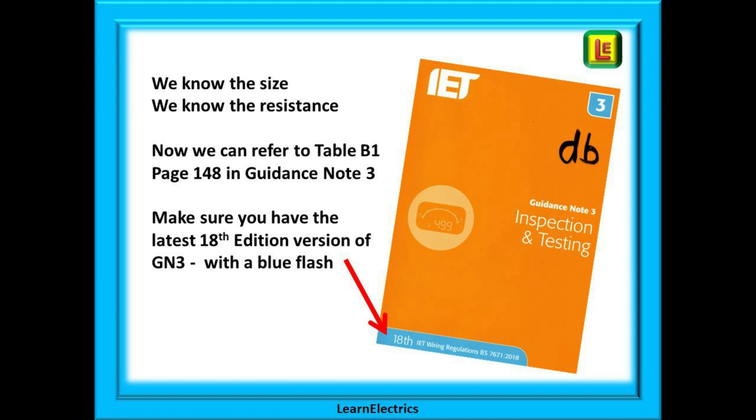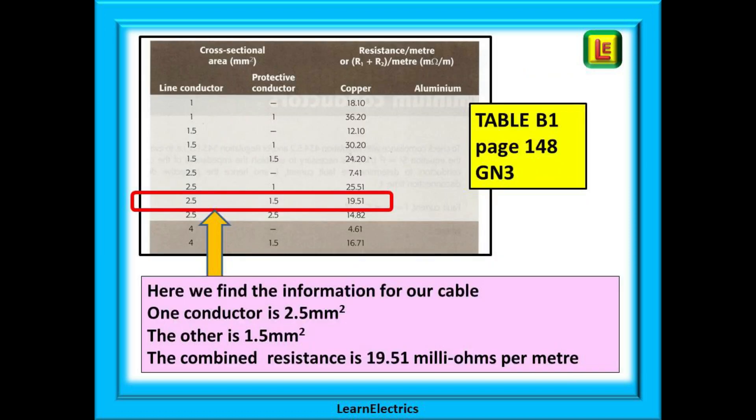Now you will need guidance note 3. I am using the version to 18th edition the one with a blue flash on the front and if you turn to page 148 you will find table B1. Here we can find the information that we need to process our resistance measurement and find the cable length.